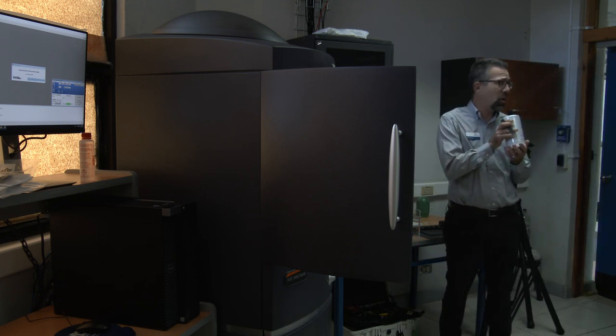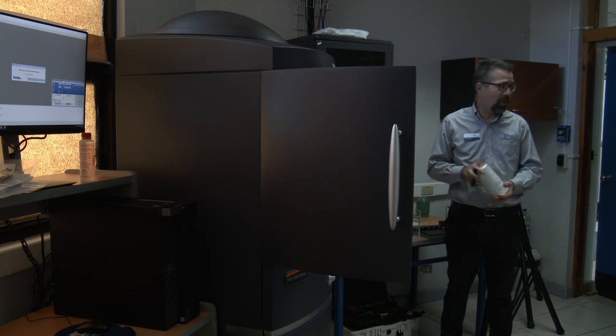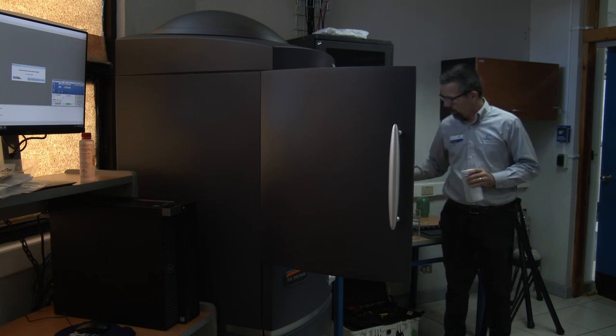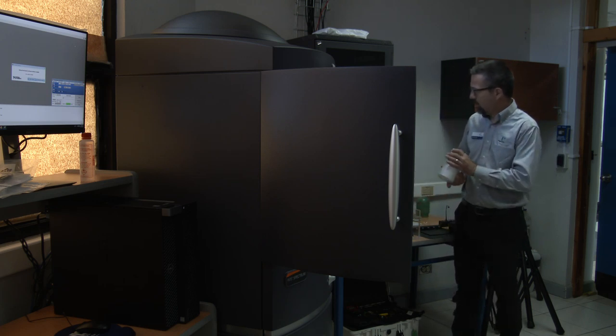First and foremost, you want to weigh this. This is your protection. So at the beginning of every day, before you turn anything else on, you want to weigh this. And if it's more than 100 grams increase, there's a spare one right here that you can use in the interim, okay? So that's your first protection.